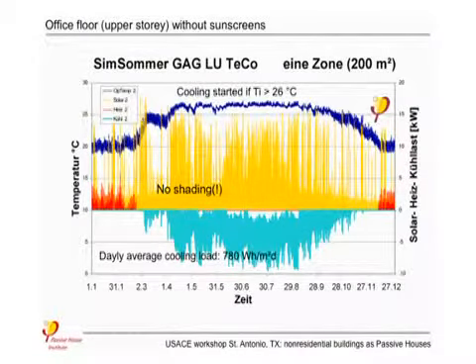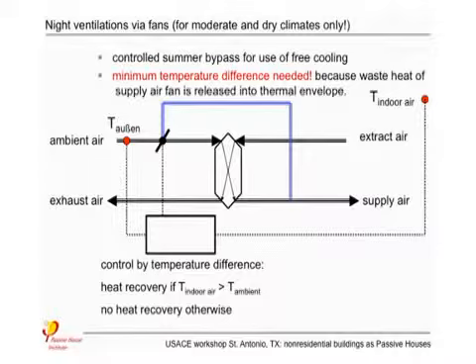We are at low numbers of cooling power, and we have to check carefully that the goals are met. Just some hints: you may run your ventilation system with or without heat recovery, and operate it with a summer bypass in summer time, so you get cool air into the building if you are not able to open windows. But you should check, if you run this system, you will have a delta T, a delta temperature added because of the waste heat of the fans. But in principle, this is possible.